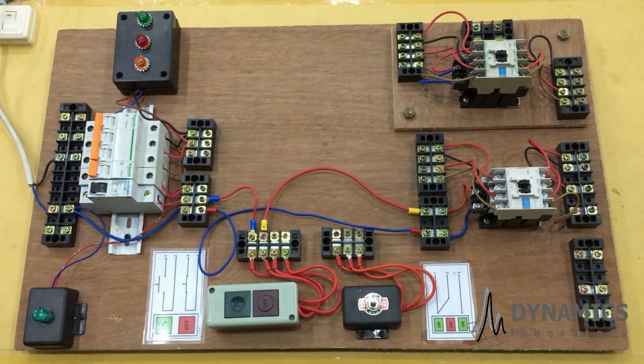Control circuit. We will create three types of control circuit. Push button, latching or push button S switch, and switch. Basically, the purpose of control circuit is to turn the contactor on and off. The on and off condition of contactor will be determined by the coil. That's why we will connect the control circuit with coil contactor.